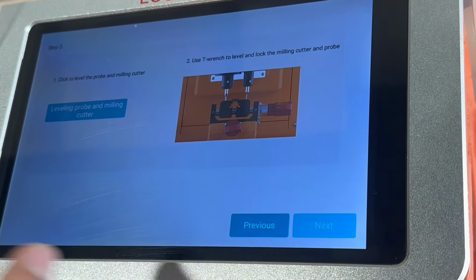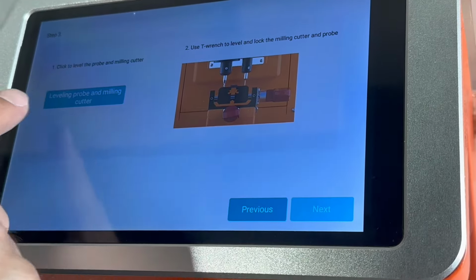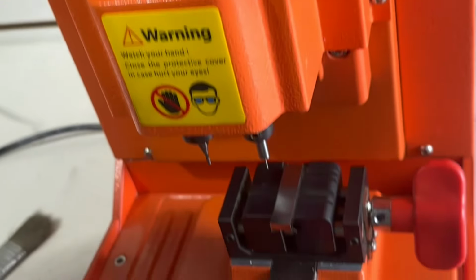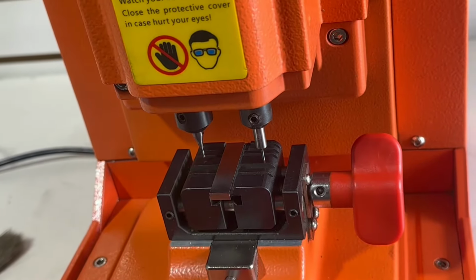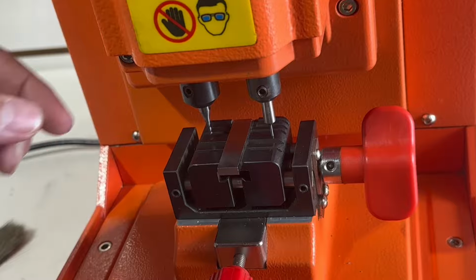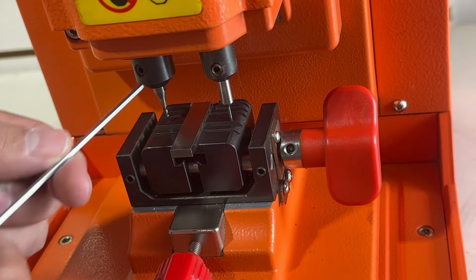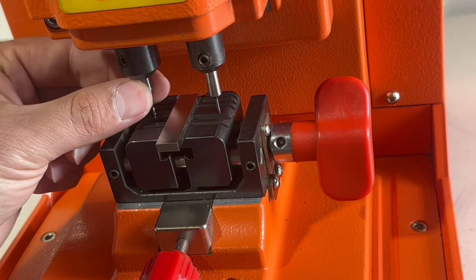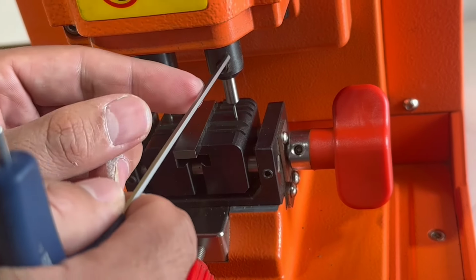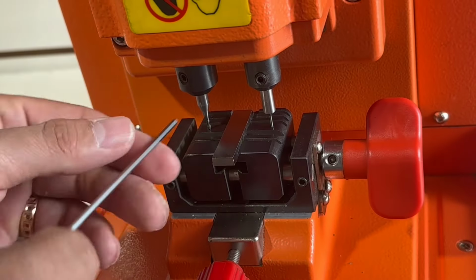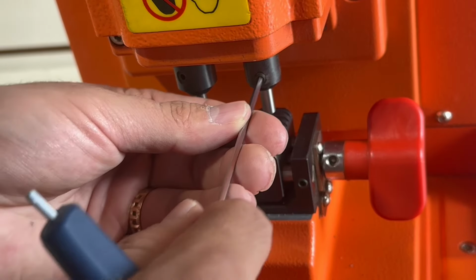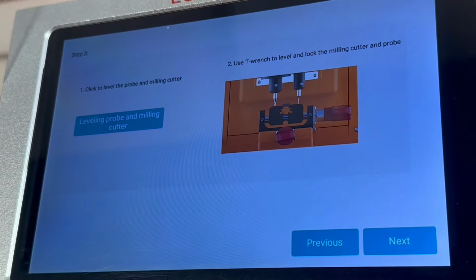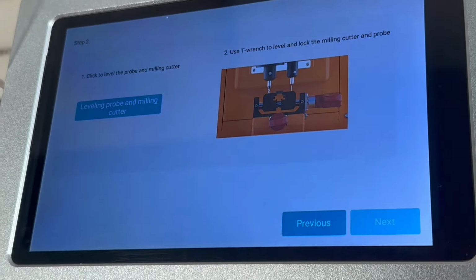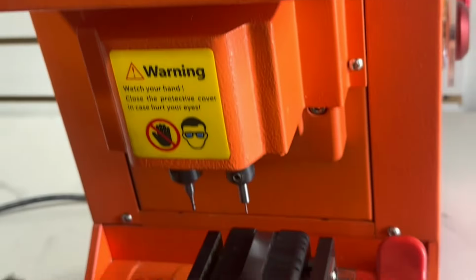So we're going to go next step. Here says leveling the probe. So click on leveling probe. So number 1, step 3. You're gonna enter. Machine is gonna do its own adjustment and it's gonna go on stop once any of the probe or milling cutter hits the stage. Then you just loosen here and bring the milling cutter down so it touches the stage. Do the same thing with your probe. Make sure it touches, and you tighten both of them. So it says use the T-wrench and tighten the milling cutter for the second step and adjust. Then now you're going to enter next. So the machine will go back to its spot.